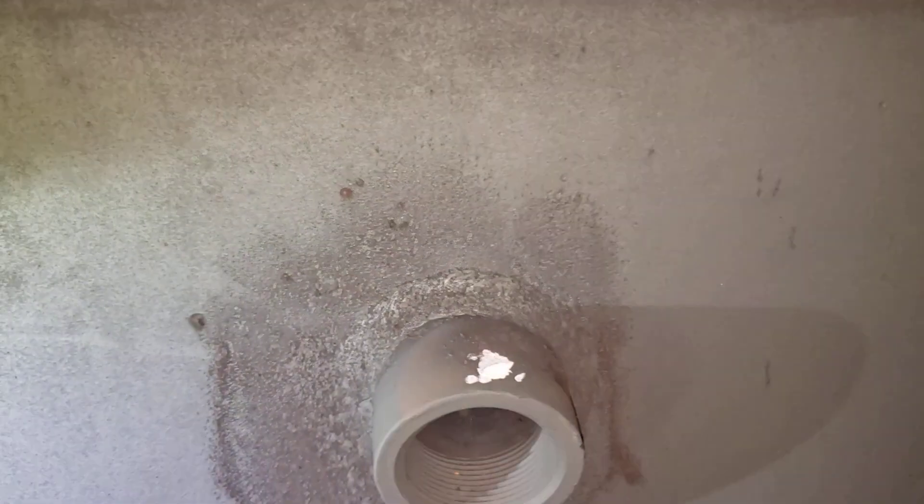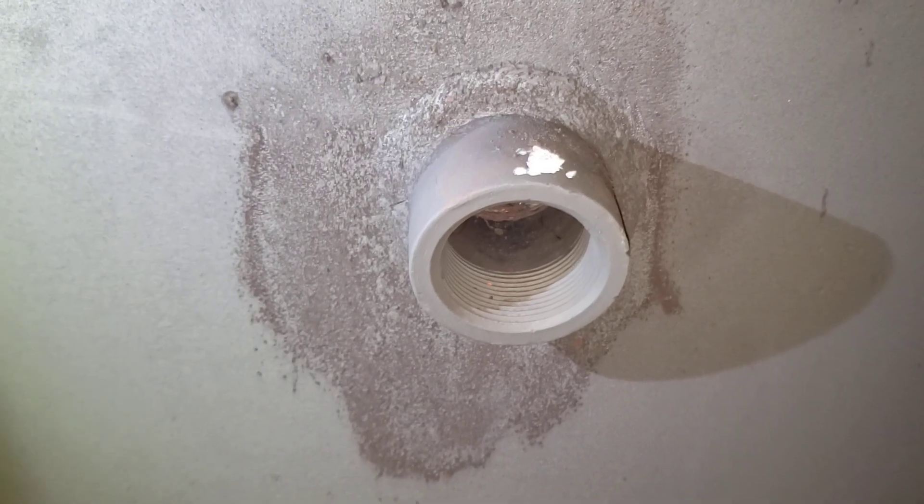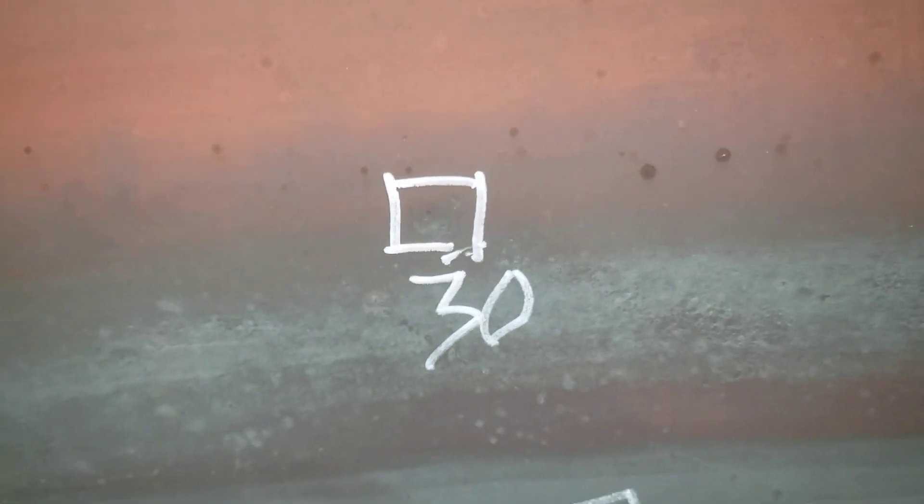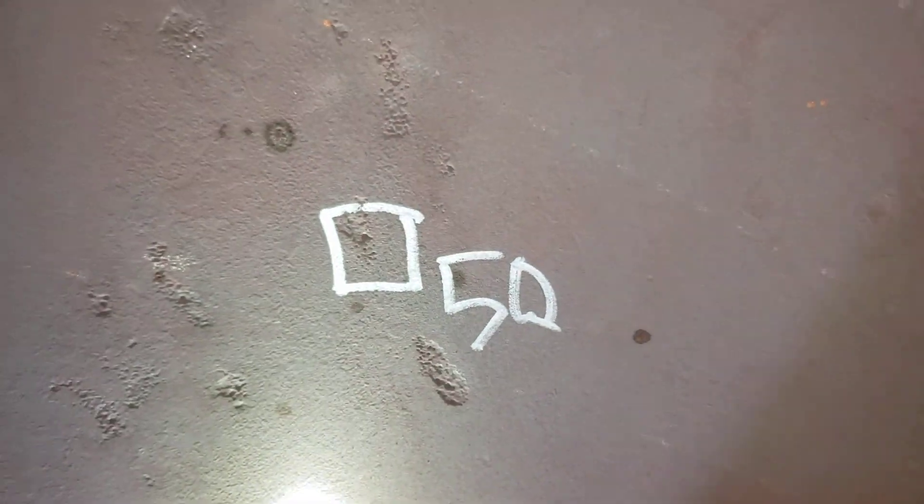The rest of the conditions are pretty typical from what I see. This vessel is actually fairly new — it was built in 2020. But if I look at the other head next to the manway, these have some corrosion, and they range between 15 and 50 mils deep. I wanted to show you guys these because they're a little more concerning, because this vessel is only three years old. They're everywhere — above and below the liquid level — and they range from 50 mils to 15.